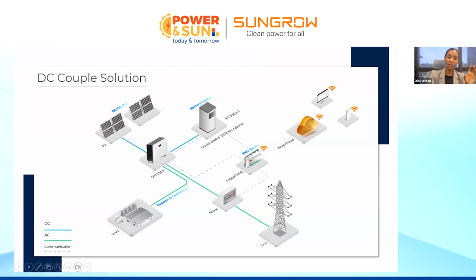The backup port is interconnected with your battery. So if the grid goes off, the on-grid load will go off, but the backup load will depend on the battery to be fed. So we also call it, in other terms, the emergency port. Why is that? Because some of the customers would like, for example, to put their full load on the on-grid port, but some of the loads are emergency loads. For example, let's say we have some medication in the refrigerator. Let's say we need the air conditioners if the grid goes off. All of those we can connect to the backup port or the emergency port, which is interconnected with the battery. So even though the grid is lost, the inverter will now use the battery to feed the backup load requirements.